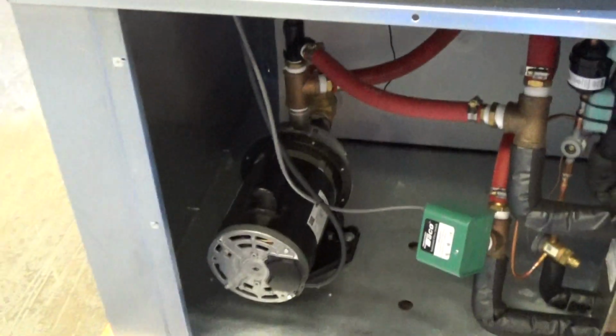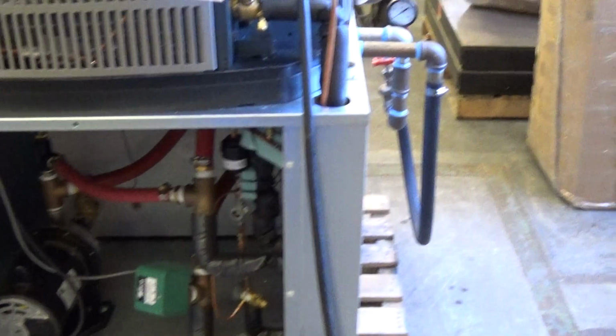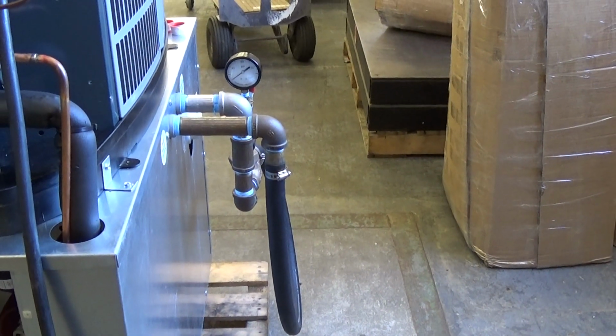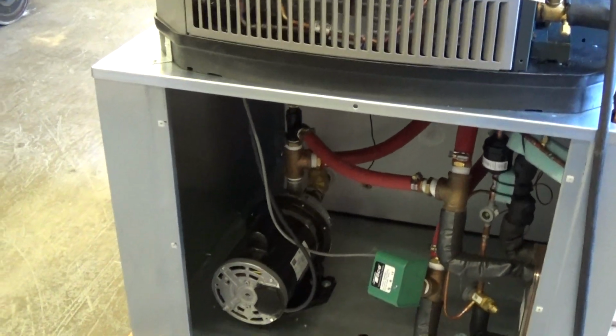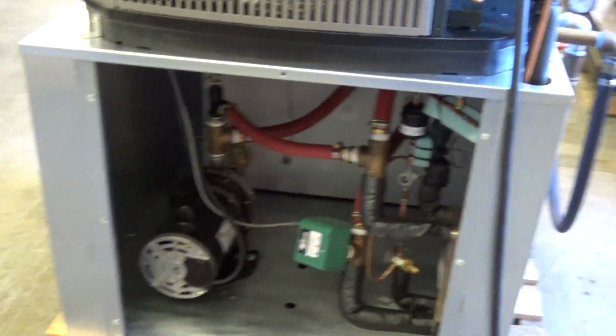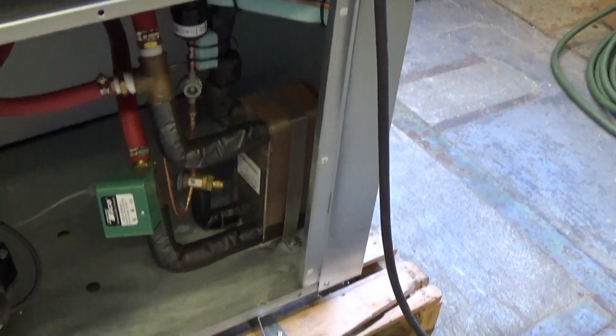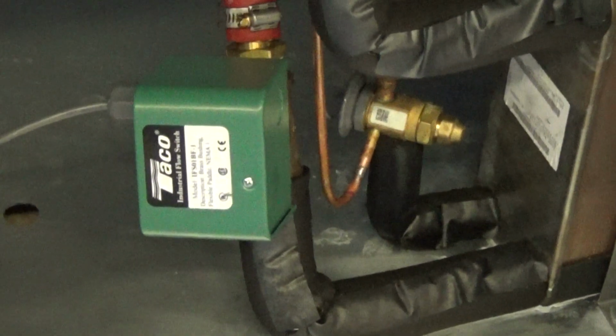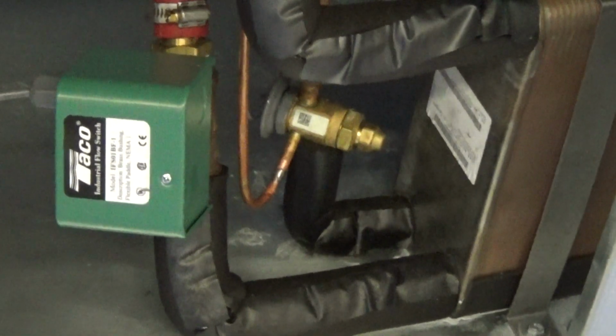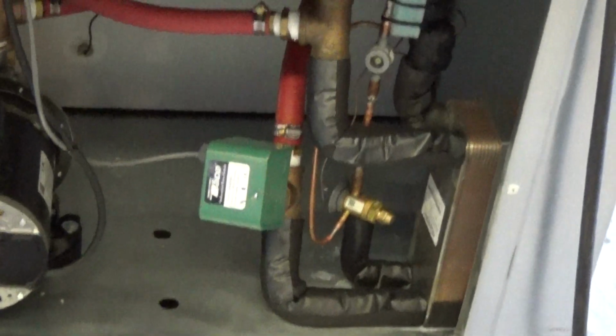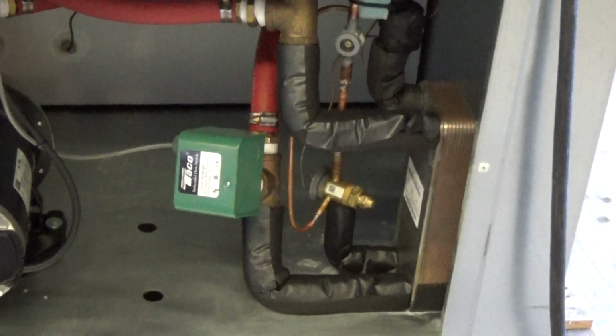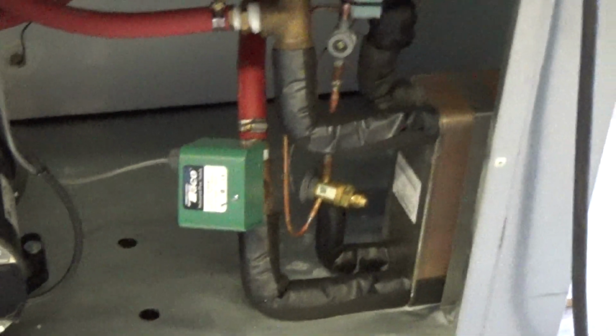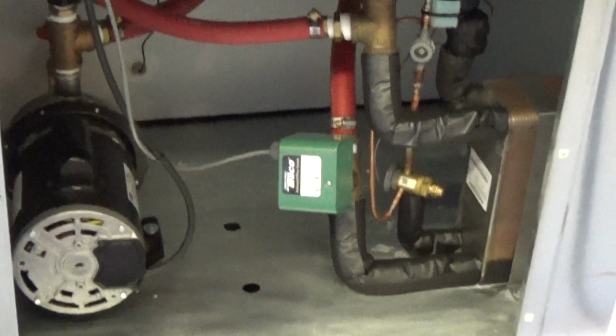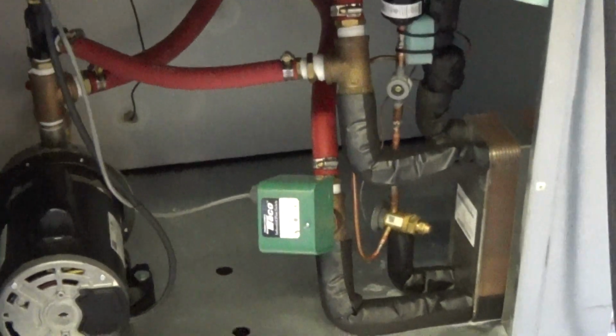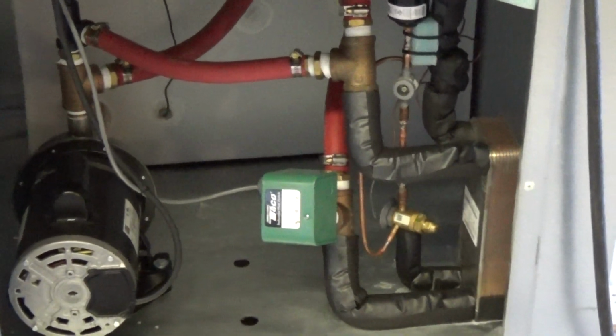So if the flow stops or is restricted going out to your process, in this case our process is just a test loop, that valve would open up, it's spring loaded, and we would get enough flow and GPM back to the heat exchanger here. This unit does have a flow switch for safety. That flow switch is also set at the factory for approximately 2.4 GPM per ton. If that flow switch is tripped, meaning not enough flow, it will shut down the 24 volt power to the unit, and the refrigeration will not run. The controller will power down. However, the pump will still run until you diagnose what the problem is.